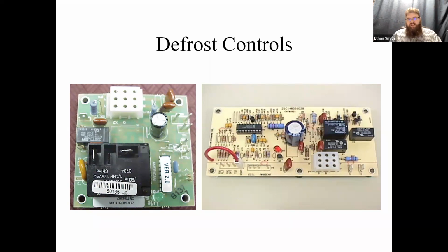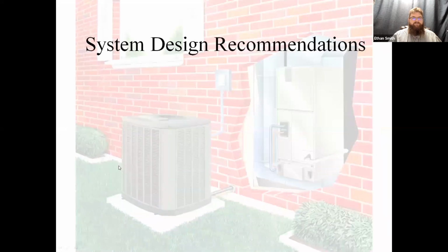So defrost controls, guys, they come in lots of different flavors. I've pulled a couple of the more common ones from the Trane American Standard stuff that I typically support and put them in here. This is kind of the older generation of defrost controllers that we saw for a long time in the Trane American Standard units. They've kind of evolved a little bit, but you notice they are backwards compatible with no conversions. We've got the same pin out on the plugs, and then we get a couple little different locations of spade terminals. So spade terminals that were there are now on top of this relay, and we get some other stuff going on. We do get some added features with the new boards that we'll go over a little later.